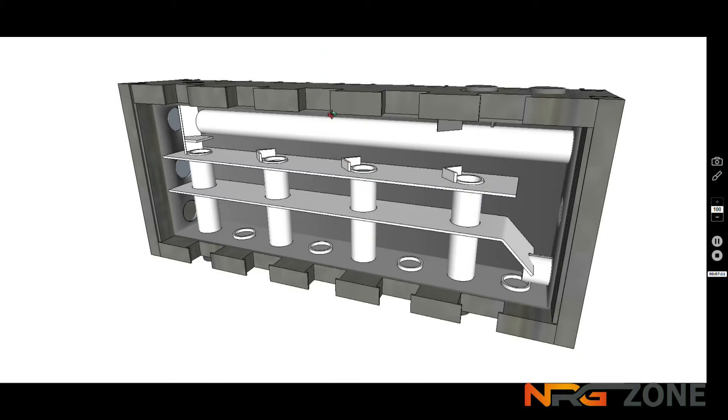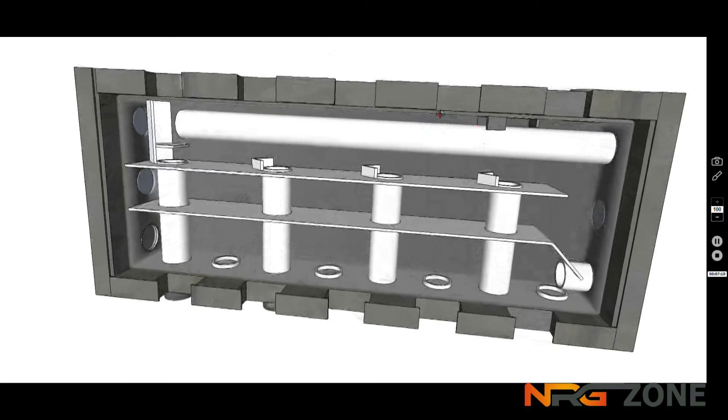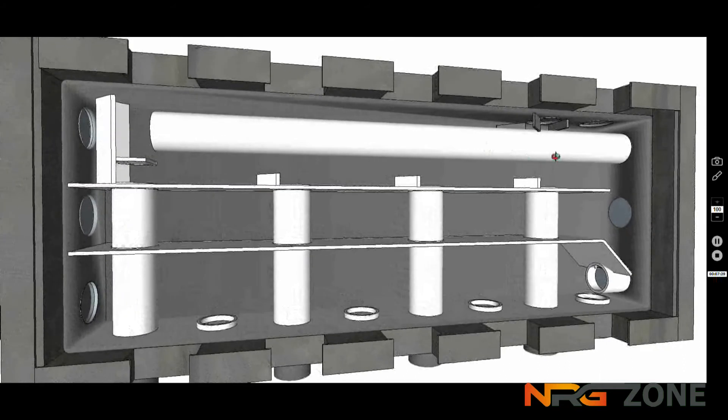But when the water is passing, it offers itself to this zone pipe, or the second zone, or zone three, zone four. In that situation, the water passing through, if there's any air in it, it passes an air scoop, which is built in, and does not need additional equipment besides the standard automatic air vent on top. And as water is traveling along, this chamber is about four or five times greater than the pipe delivering, so the water slows down by that amount. And if it does, air collects here, is scooped, and is delivered out with a standard off-the-shelf automatic air vent, which you would fit at this point, in all situations.